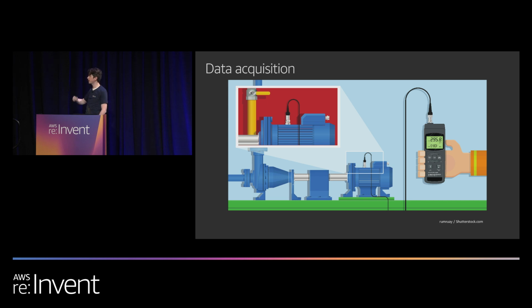This is an example of a very manual process. I have to take the kit, walk up to the electrical motor, attach the transducer, download the logs, take it back to my PC, and upload over some kind of serial connection. In more sophisticated methodologies today, there are wireless vibration transducers that can be affixed and just constantly emit the vibration coming off of that device.